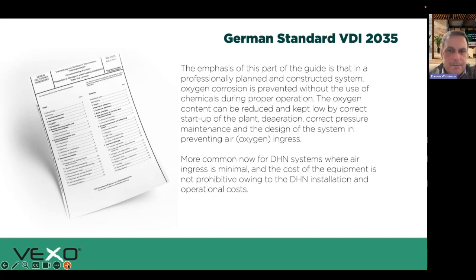But that is the non-chemical treatment approach. The only downside to consider is the ongoing maintenance—you don't want a dosing pot if you can have a VDI standard approach instead, because the minute you add chemicals into a system that's using VDI, it throws the whole thing out and causes issues.